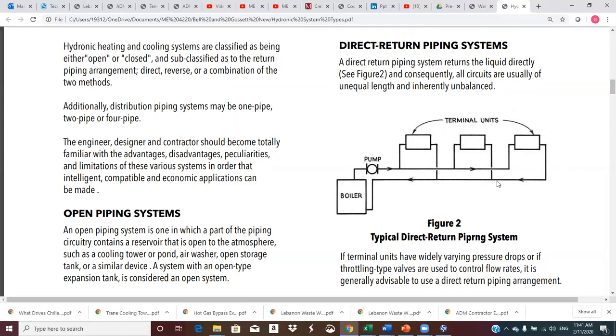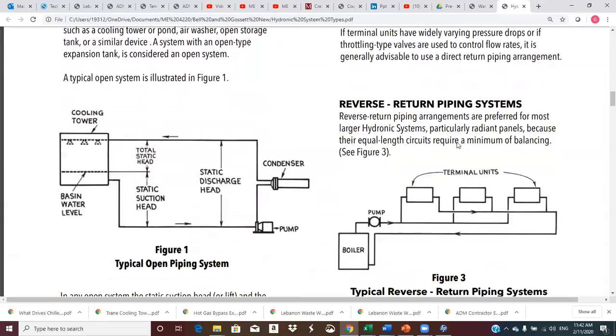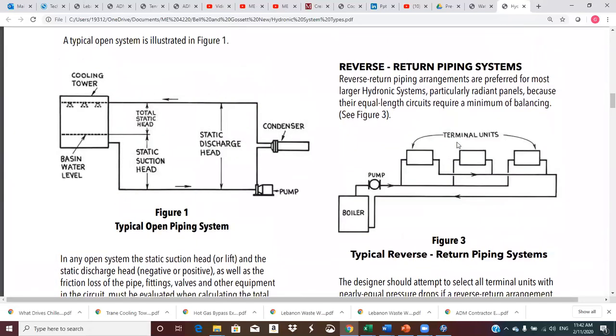And when we see a reverse return, then it'll become even clearer. Let's see, what other comments? He says if terminal units have widely varying pressure drops, or if throttling type control valves are used to control flow rates, it's generally advisable to use direct return. So if these coils have widely varying flow pressure drops, then it's okay to do this. This saves pipe. We have less pipe compared to the reverse return. So let's look at reverse return here.